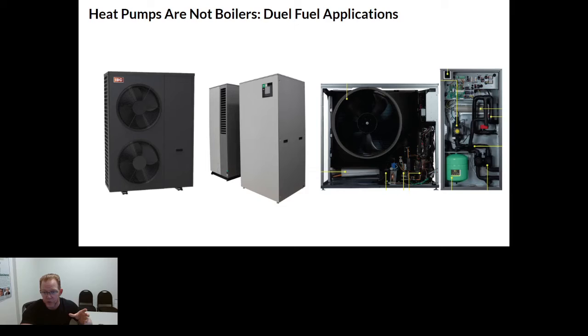The System M, which you see right next to it, in the middle, it's the same concept. Their indoor unit has all of the controls and the logic built into it. So you don't have to worry about what am I doing for backup heat? How am I piping the heating? How am I piping the cooling? That's not necessarily a pro. It depends on your scenario, right? The IBC can be a better advantage depending on who's watching this video and what your skill level is. And then on the right-hand side, we have the Enertech unit. The Enertech unit is a packaged unit. So outdoor unit, indoor unit, all of these units are cold climate variable speed, just to be clear.